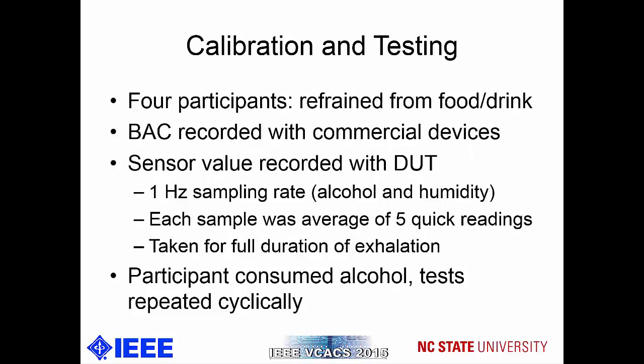So, to do this, we had 4 participants who were administered incremental amounts of alcohol, with a 20-minute time lapse in between doses. This was to eliminate interference from mouth alcohol. After each dose, the sensor value was recorded using our device, and the BAC was read by the 3 commercial off-the-shelf systems.